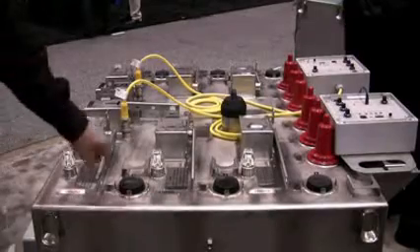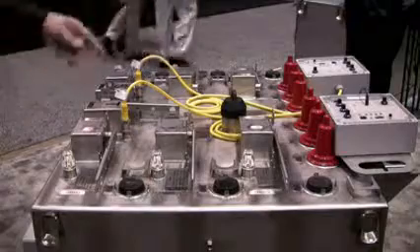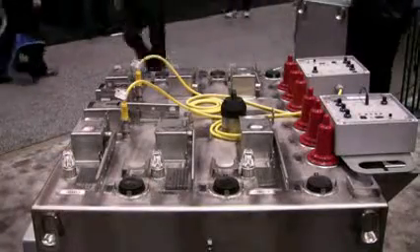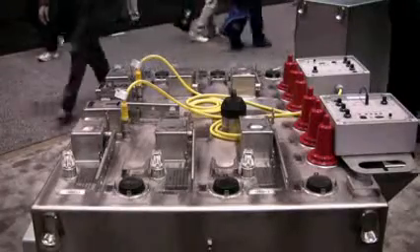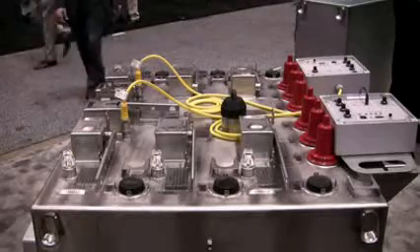The VFI ways — you'll see there are three handles. We have a device that grabs all three handles to be able to open and close all of them together. Or if it's being operated as a single-phase device, you would trip one phase on a single-phase overcurrent, and then you could reset that particular phase.